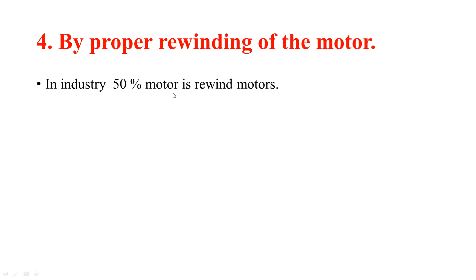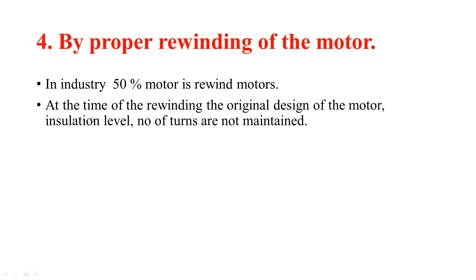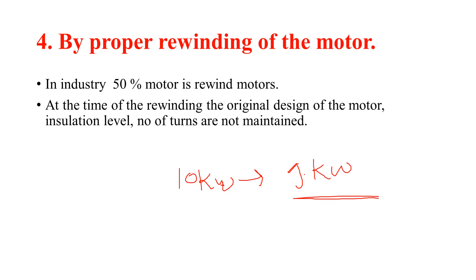The next point is proper rewinding of the motor. In industry, 50% of motors are rewound motors. At the time of rewinding, the original design of the motor — insulation level and number of turns — are not maintained. For example, if the load is 10 kW but after rewinding only 9 kW is available, the motor will be overloaded.